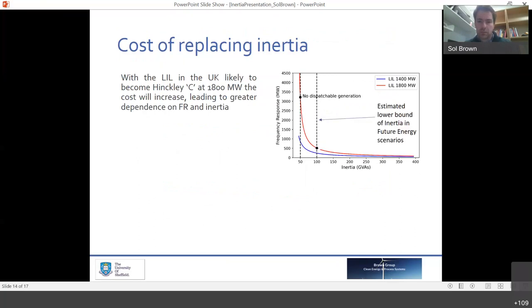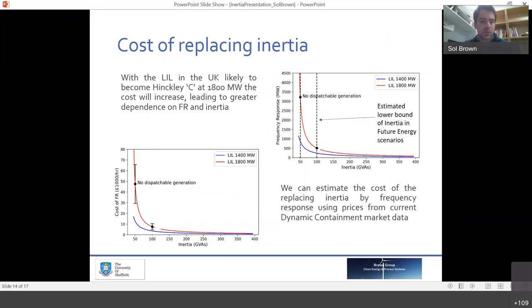And then lastly, you can map, using the marginal cost of the frequency response, the actual cost of providing frequency response against the amount of inertia that you would be replacing. In some cases where you have no dispatchable, by dispatchable I mean gas turbines, you're looking at an increased cost of maybe £40,000 per hour for the duration, based on current dynamic containment market data. So we can actually calculate the cost of replacing inertia by frequency response, and you can see the shape of the curve. It's exponential where you have low inertia.